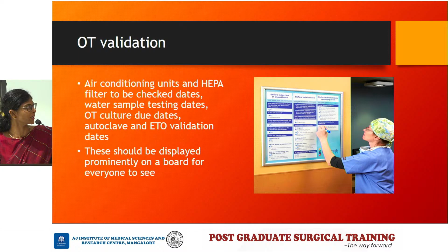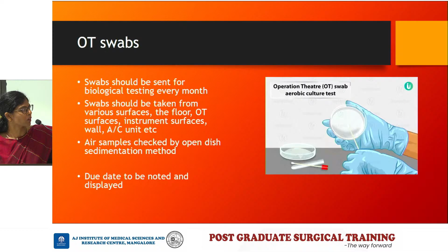And OT swabs ideally should be sent for biological testing every month. They should be taken from both sterile and unsterile surfaces. So the floor, the OT surfaces, wall, AC unit, everything. Air samples also need to be checked by an open dish sedimentation method. And again, the due date needs to be noted and displayed.